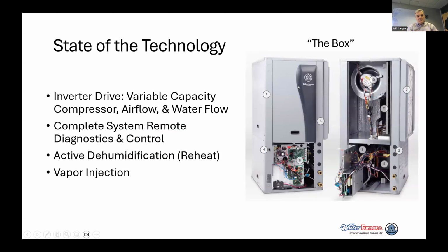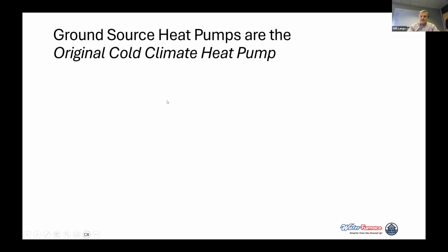Technology has changed dramatically—both Water Furnace and our competitors have upped the game. We have inverter drive compressors, variable capacity airflow and water flow. Everything now operates on an as-demand basis if you choose an inverter type heat pump. We can control these units from a cell phone, whether in a pickup truck in Paraguay or from the beach in California—you can see everything there is to see on these units remotely. We monitor them every 10 seconds. We do active dehumidification, something new to the industry with reheat coils, and now vapor injection. We've caught up to and perhaps even surpassed European technology with vapor injection, which allows very low temperature performance for ground source heat pumps—they're the original cold climate heat pump.